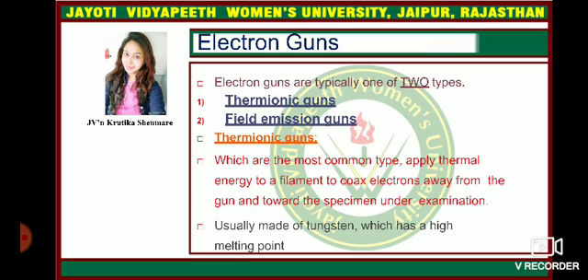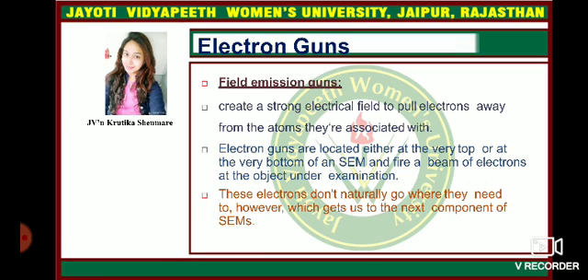The electron guns are typically one of two types, the thermionic guns and the field emission guns. The thermionic guns, which are the most common type, apply thermal energy to the filament to coax electrons away from the gun and toward the specimen under examination, usually made of tungsten, which has a high melting point. The field emission guns create a strong electrical field to pull electrons away from the atoms they are associated with. The electron guns are located either at the very top or the very bottom of the SEM and fire a beam of electrons at the object under examination. These, however, don't naturally go where they need to, which gets us to the next component of the SEM.